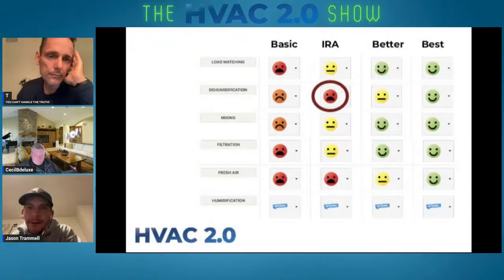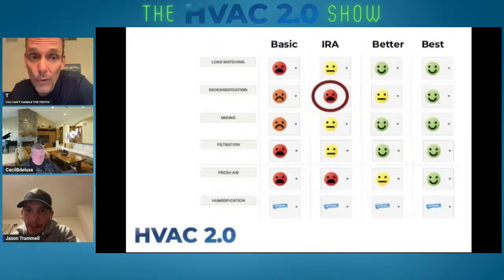And to get those ratings that the equipment manufacturers are trying to attain, you have to move more air across, because they don't care about latent capacity, which they actually do care about. They don't want energy going to it, because condensing moisture from vapor to water takes a huge amount of energy, 800 something BTUs per pint. That's why whole house dehumidifiers are pretty inefficient, because they have a small coil that sucks moisture out of the air. They run low airflow across a small coil, and then heat it back up with the condenser coil, because that's how you remove moisture.